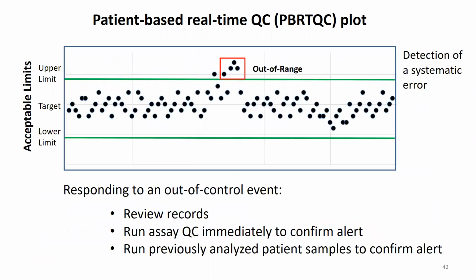So here's an example of a patient-based real-time QC approach where the mean of every 40 patient results is plotted over time. The graph shows the limits of acceptability, and results that exceed those limits will create an alert. An out-of-range alert indicates a systematic error larger than the normal variation of the analyte in the patient population, and this condition could represent an analytical measurement issue. You can see here that the tool detected a systematic error. So the tool can detect an analytical problem earlier than routine statistical QC because it's being performed with a defined number of patient sample results, like every 30 or 40 patients. However, the technique can produce false alerts.